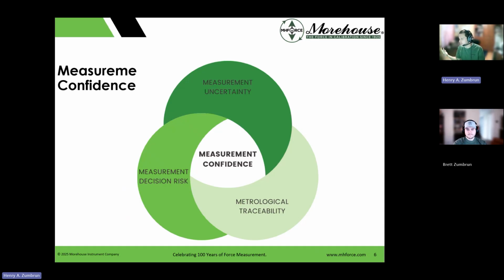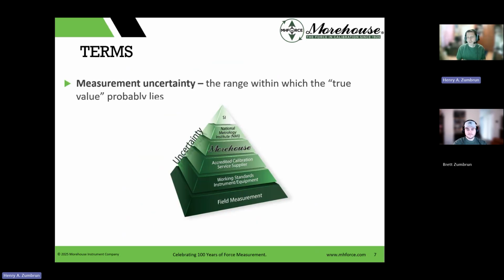So there's three pillars. Those are the three. And if we review them quickly, these are available online. Measurement uncertainty. This slide says the range within which the true value probably lies. If we want to claim it, we trace it back to SI units, not NIST. Some people say traceable to NIST. We all know that's wrong.